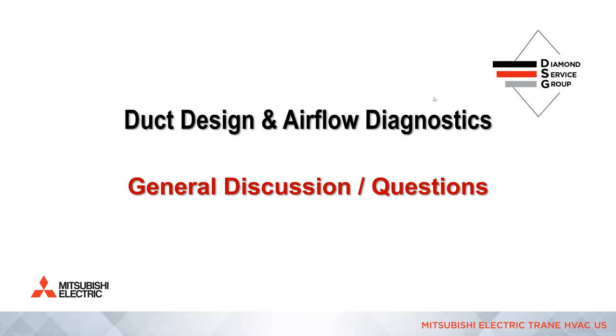It's awesome. I don't know if you saw the question. I see Andy said, we have insulated basement trunks to R15 or R20 to keep the temperature drop down in ducts where the basement is semi-conditioned. Yeah, Andy, that's a really important point with variable speed systems, because the majority of the year you're running at part load, right? 98% of the year. We design for the 99% design temperature. So when the fan speed turns down, the air is in contact with that ductwork for a longer period of time. And if you have poor insulation on it in an unconditioned space, even if it's within the building, you end up having higher losses than you expect.